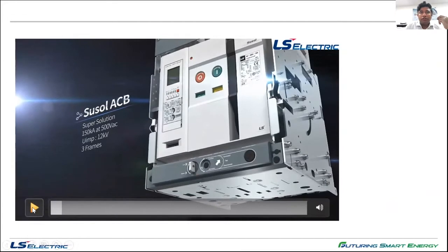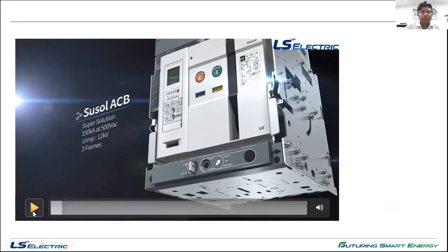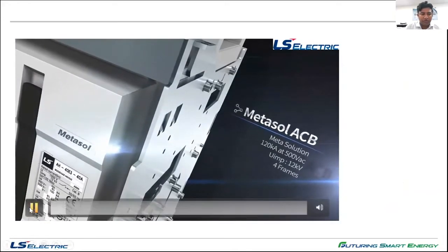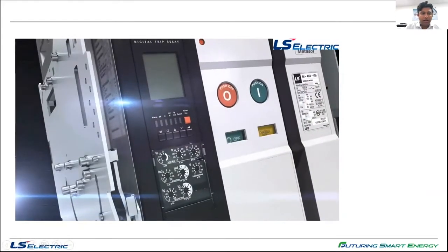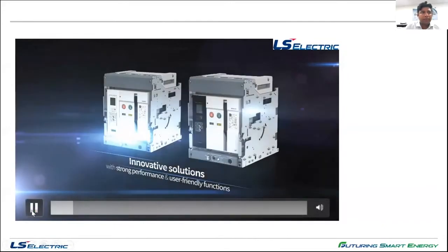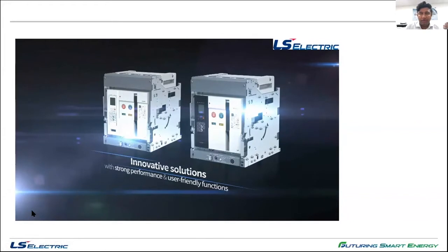So during the video, I will pause and explain what the different types of breakers are that we have. In the first, what you can see here, we have basically 2 ranges. One is Susol, another one is Metasol. In Susol ACBs, we have up to 150 kA breaking capacity in 3 different frame sizes. And in Metasol, we have up to 120 kA with 4 different frame sizes. So these are basically the 2 options that we currently have, Susol ACBs and Metasol ACBs.